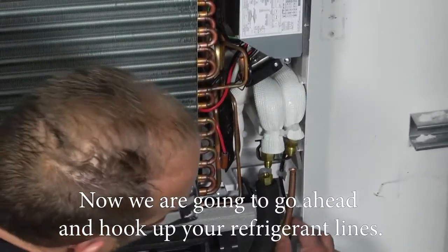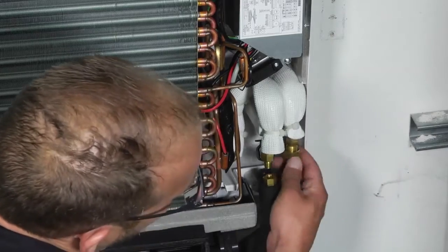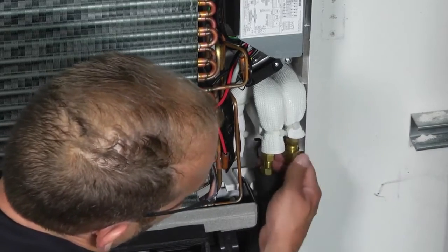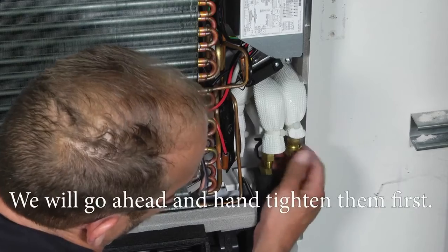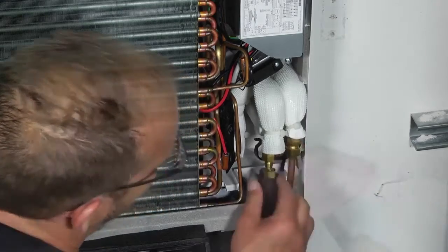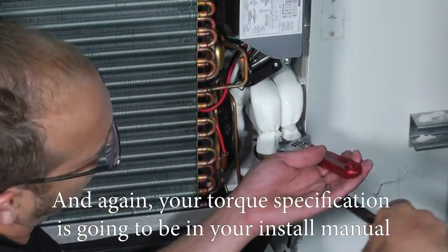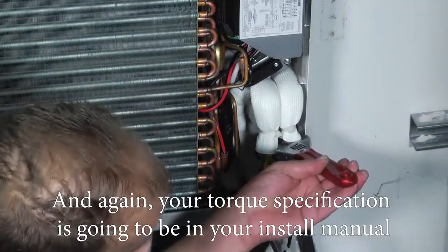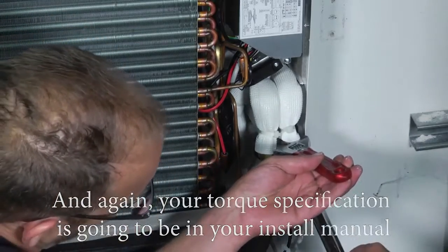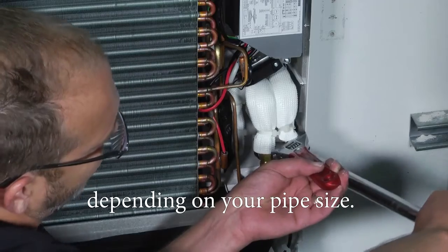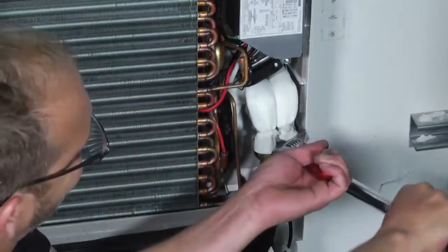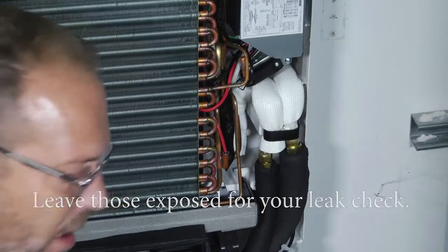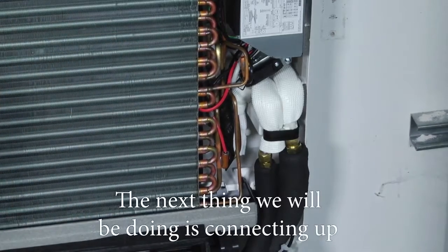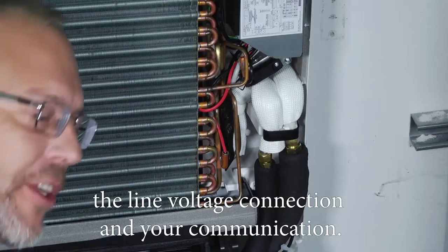Now we're going to go ahead and hook up your refrigerant lines. We'll go ahead and hand tighten them first. And again, your torque specification is going to be in your install manual, depending on your pipe size. Leave those exposed for your leak check. The next thing we'll be doing is connecting up the line voltage connection and your communication.